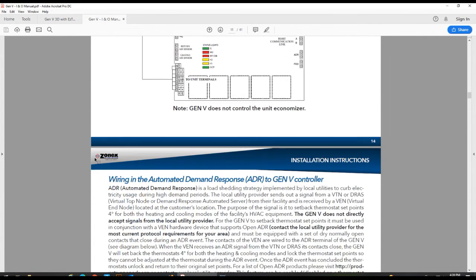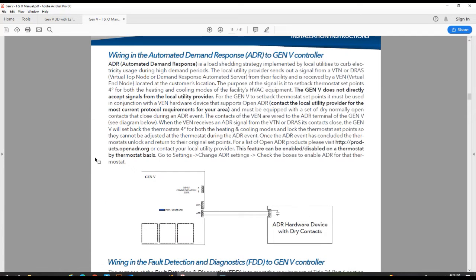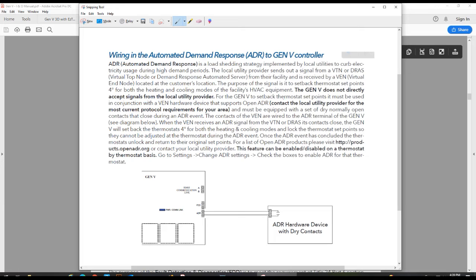Alright, moving along, there are a couple additional terminals on the Gen V controller. We have what's called ADR. ADR is Automatic Demand Response. This is utilized with utility companies. It's a third-party control that wires into the ADR terminal on our controller. When we are seeing high energy demands, the utility companies can send a signal out that will tell our controller to set back all the thermostats by 4 degrees to help reduce energy consumption during this time period. So if you need to utilize that, you can.